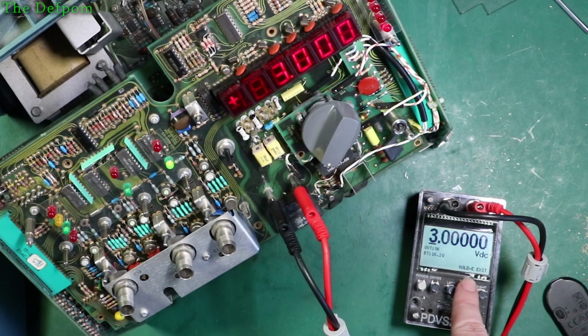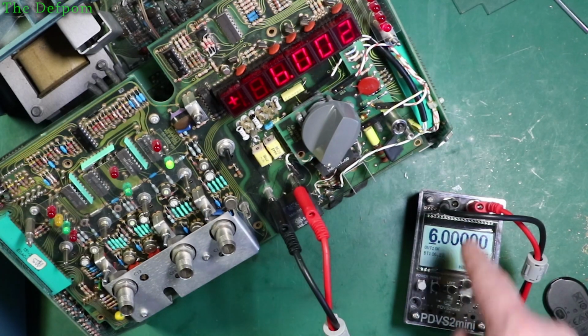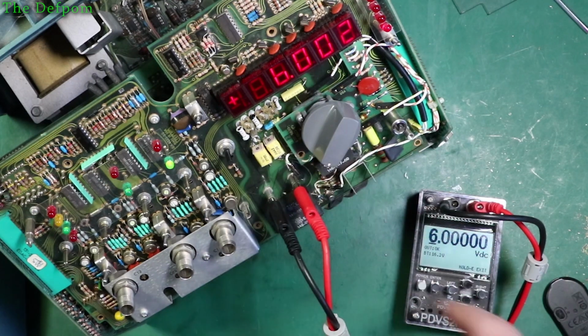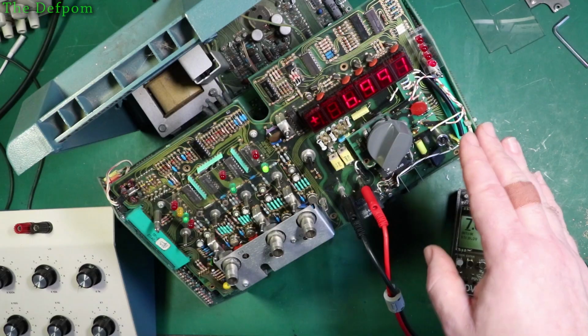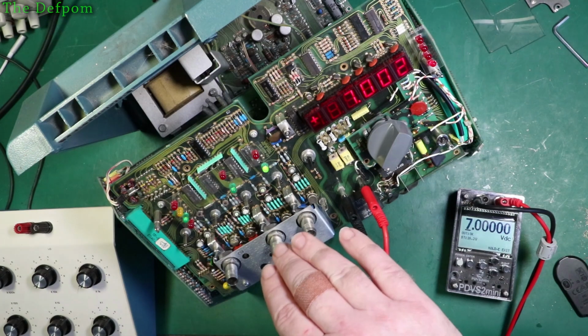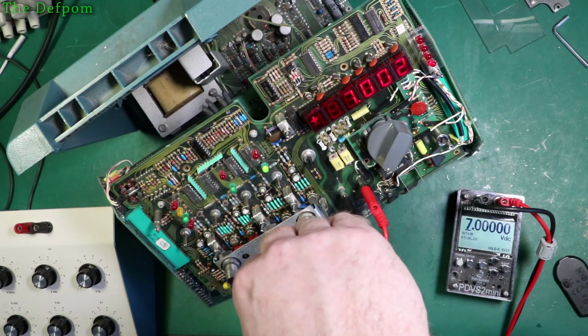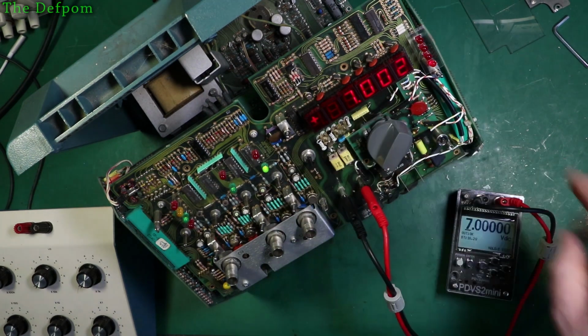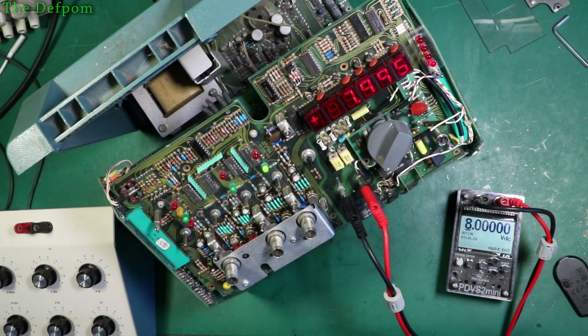3 volts is... but when I did that first range, I noticed that below 2 volts it wasn't dead linear. It's not this which is wrong, I know this is definitely right. As it increases in voltage the reading increases slightly, then as it gets to the top of the voltage it comes back down again. I'll demonstrate that in a second.